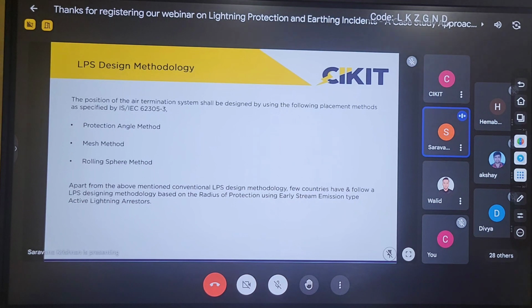Among these methods, we have been using the protection angle method for a long period. If I take the olden designs, there will be one rod at the top of the building, and this rod will provide some protection up to a certain angle. Since the protection depends upon the angle, it is considered the protection angle method. The second method is the mesh method, which simply lays the conductor in the form of a mesh over the structure to be protected. The third one is the rolling sphere method, which we are using commonly nowadays. These are the commonly used methods for designing.